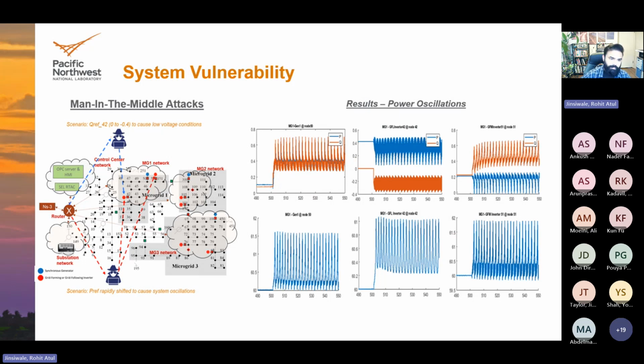It's a pseudo-optimal mode, and these are of course very large oscillations which would traditionally be captured by a protection scheme. But if these oscillations were in a much smaller band, you could have a scenario where it slips under the radar of your protection scheme, yet these oscillations still percolate through the system. Just another representative scenario to show the effect.